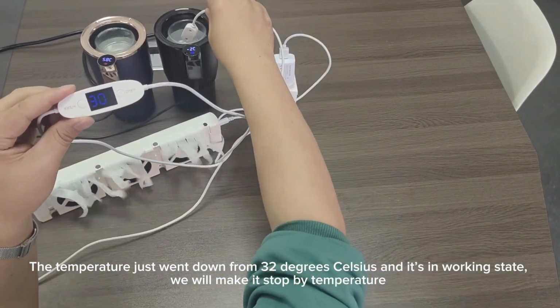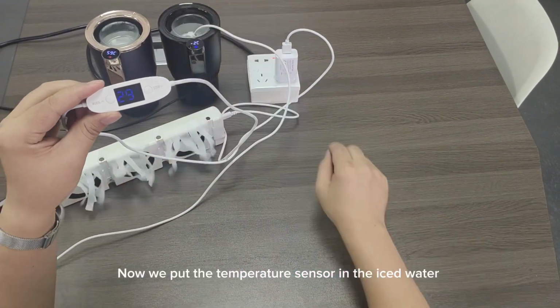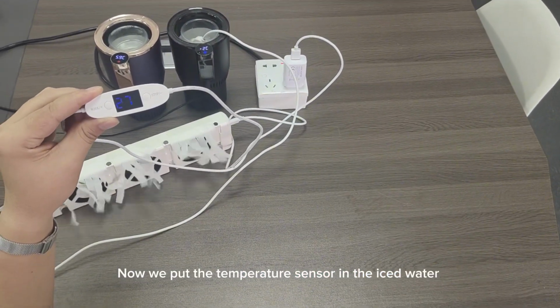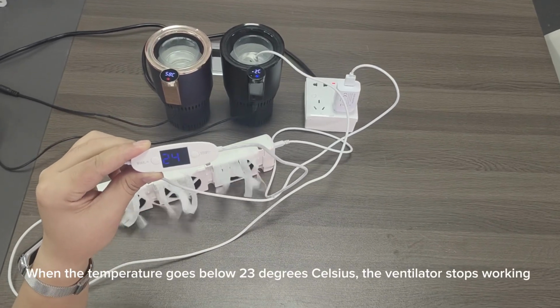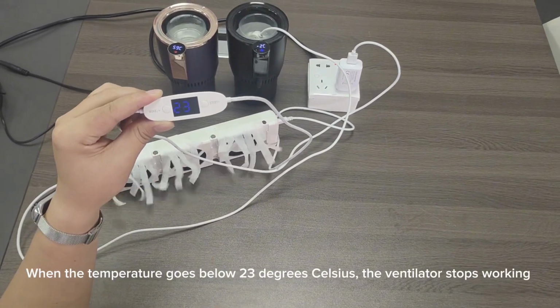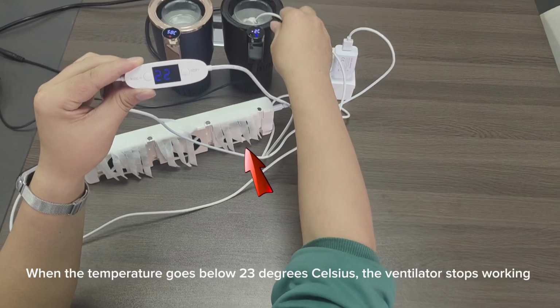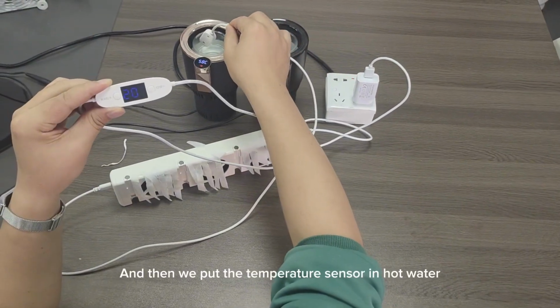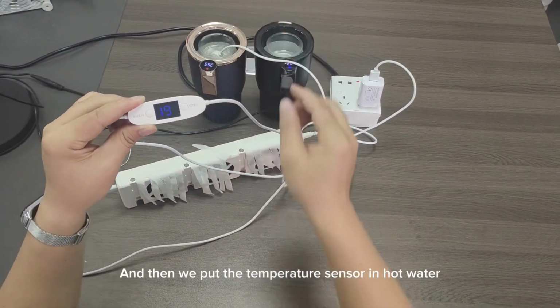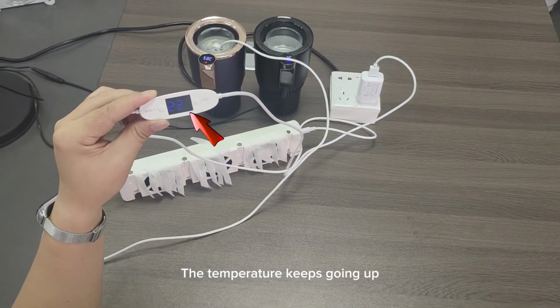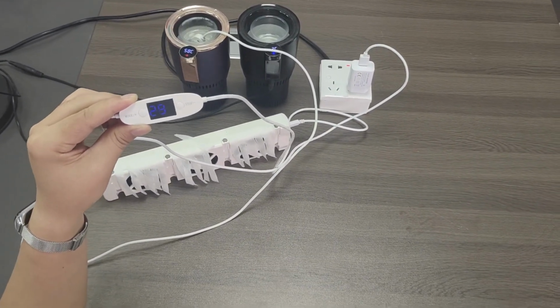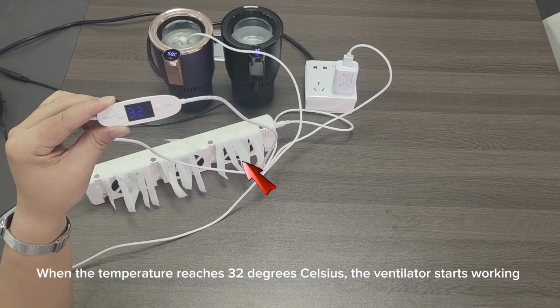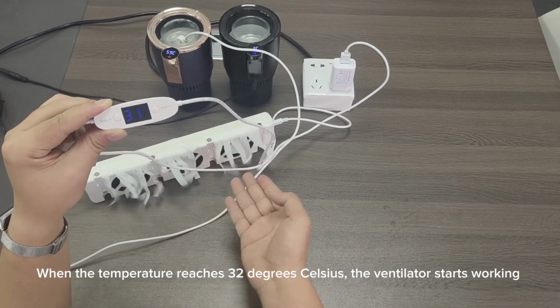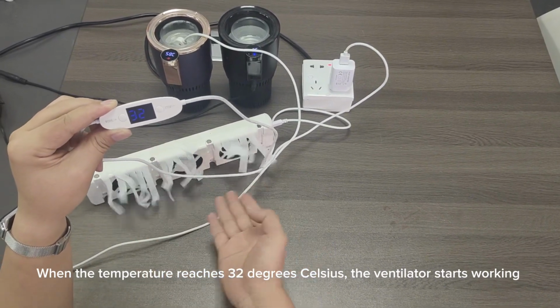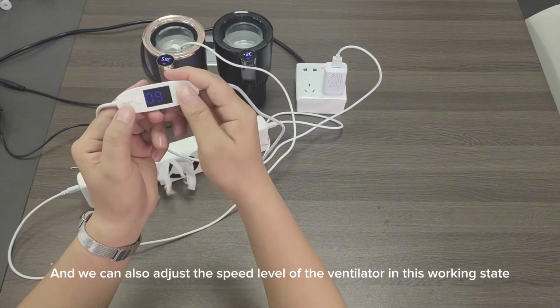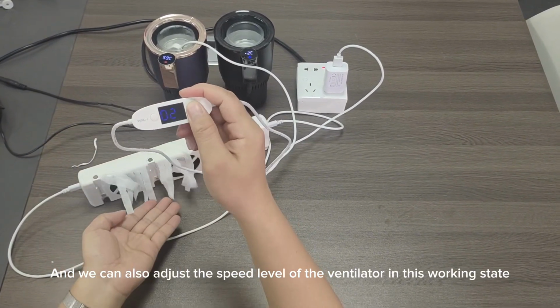We will make it stop by temperature. Now we put the temperature sensor in the iced water. When the temperature goes below 23 degrees Celsius, the ventilator stops working. And then we put the temperature sensor in hot water. The temperature keeps going up. When the temperature reaches 32 degrees Celsius, the ventilator starts working. And we can also adjust the speed level of the ventilator in this working state.